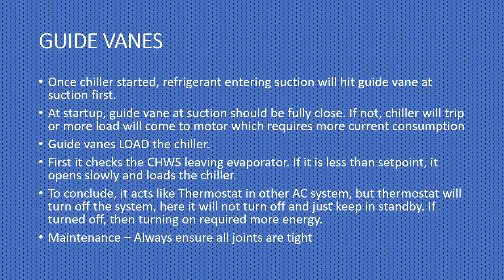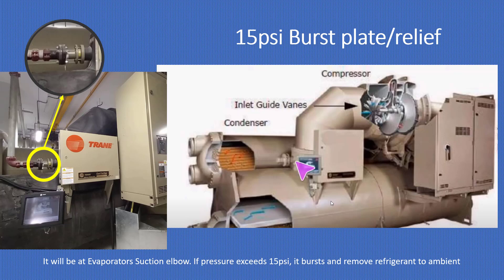Maintenance: always ensure all joints are tight. Another important component is the 15 PSI burst plate or relief disc. You can see it here — it will be at the evaporator suction elbow. If pressure exceeds 15 PSI, it bursts and removes the refrigerant to the atmosphere. This is the inlet guide vane assembly — the whole component is the compressor, followed by the condenser section.